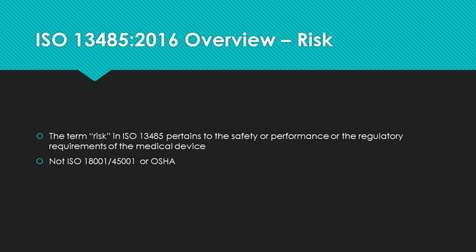The term risk in ISO 13485 pertains to the safety or performance or the regulatory requirements of the medical device. It is not talking about ISO 18001 or ISO 45001 or OSHA, but the risk of the device to the patient or user.